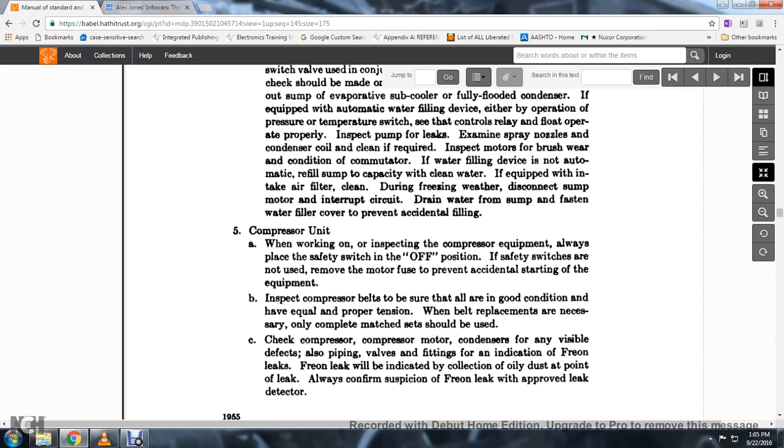14. Check for indications of freon leaks. 15. Freon leaks are indicated by the collection of oily dust at the point of the leak; always confirm suspicion of a freon leak with an approved leak detector.